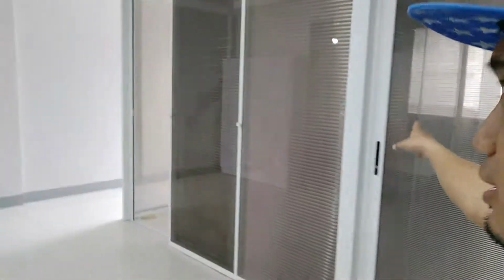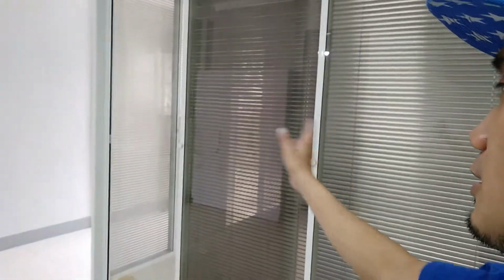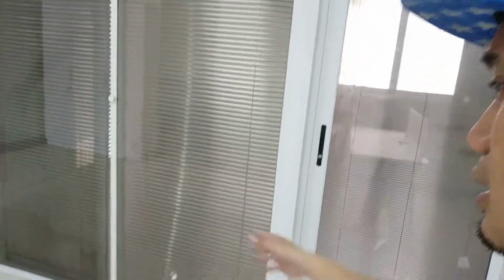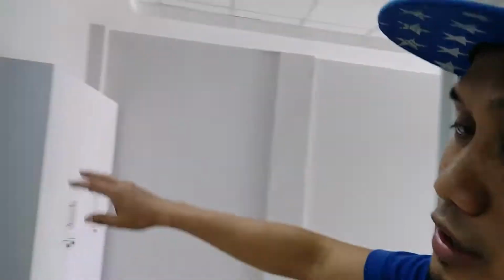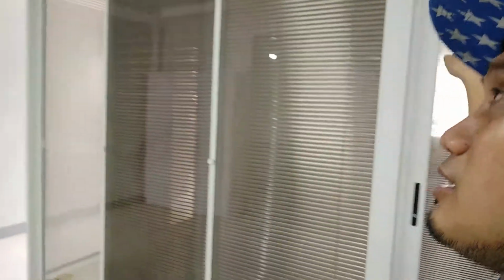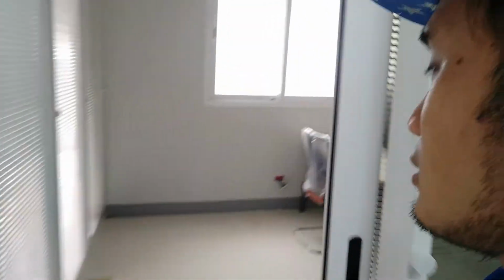And this area here, the original plan is it's going to be the agent area. So the original plan is we have 7 workstations here. So we run the cable from the server going here, like 14 cables. That's equivalent of 7 workstations, and all the wires are stuck in there. So that's the problem again. So we're going to look for any workaround also on how we can distribute all those cables to any area here that is going to be available, because this room is only 1 PC, so we only need 2 cables.